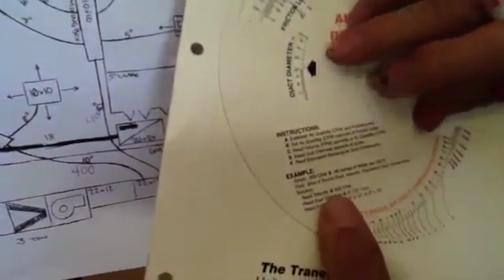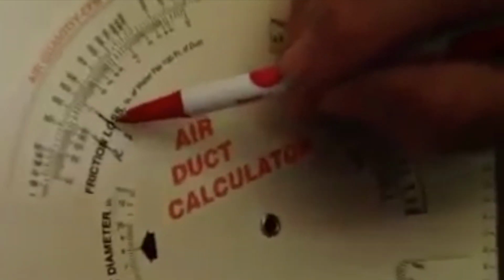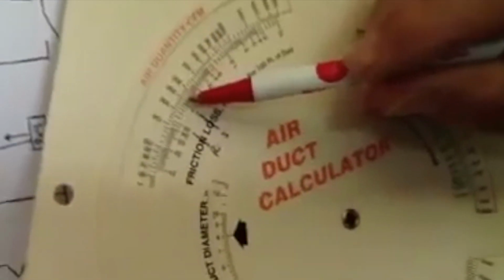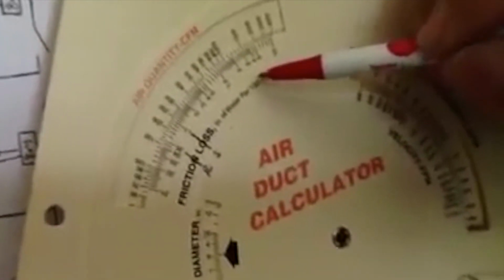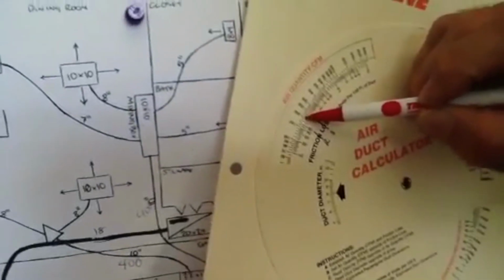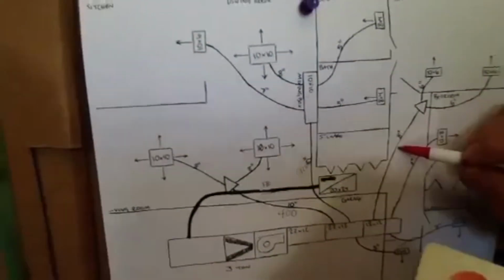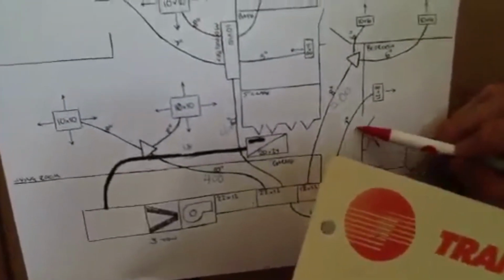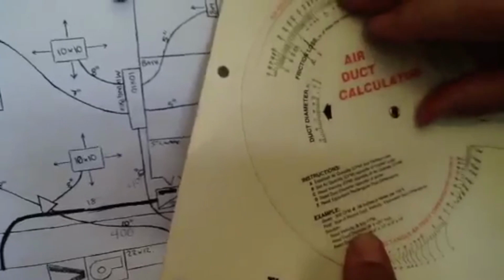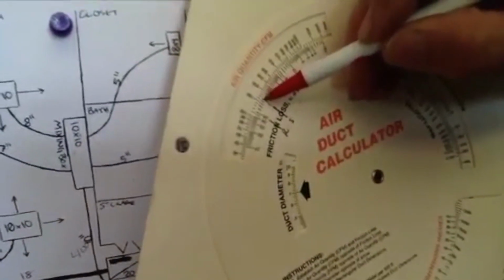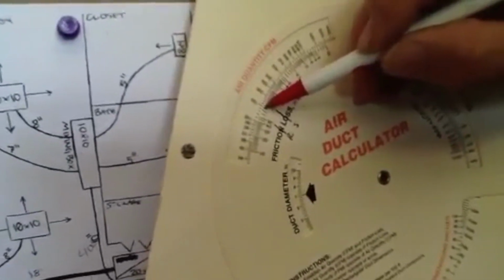Okay, let's go down here. 8-inch. At 0.1 static pressure is 240 CFMs. Now what I do to compensate for my sheet metal ductulator versus my flex ductulator, I just drop it back to 200. I never go up, I always go down, so I'm going back to 200. Now I've got a 7-inch flex here. Okay, 7-inch. At a 0.1 static pressure, that's about 165 CFMs, but I'm going to go down to 150.